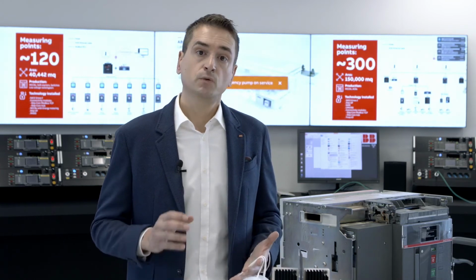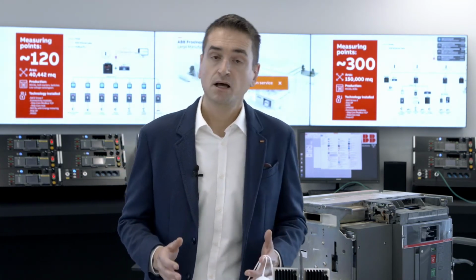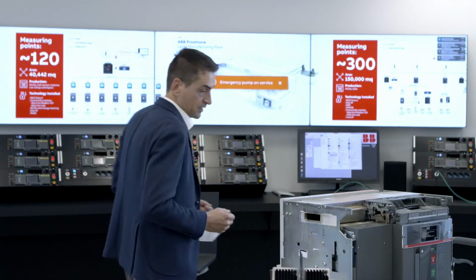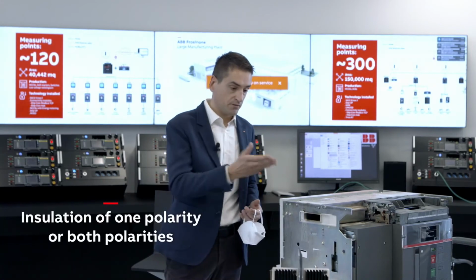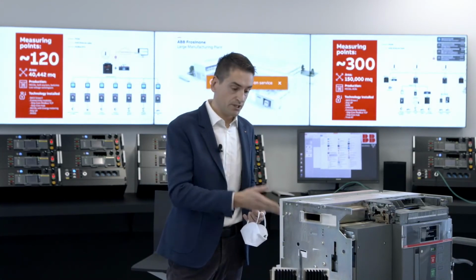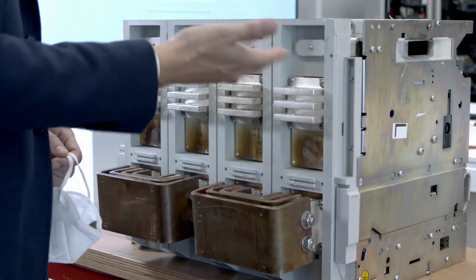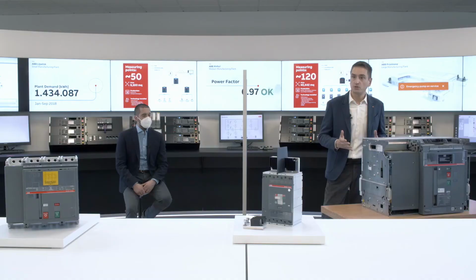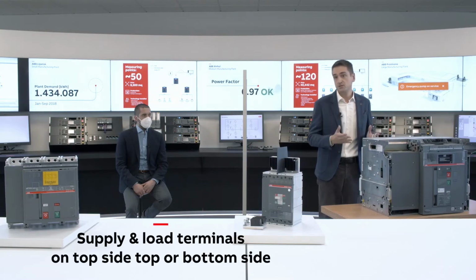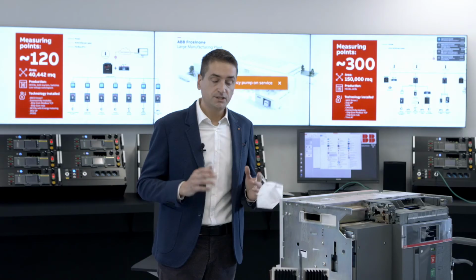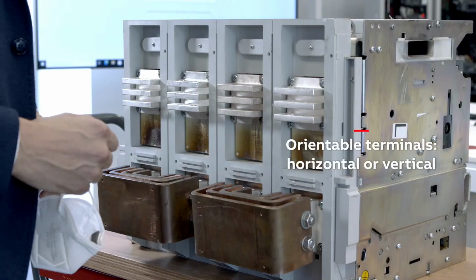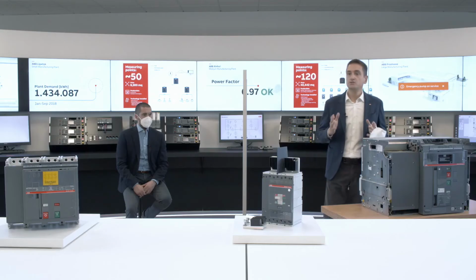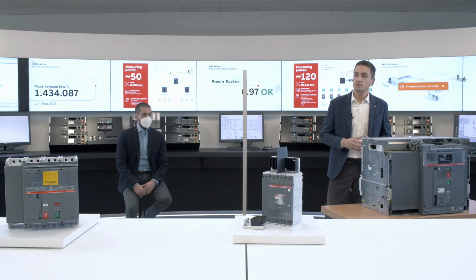One of the main aspects we try to guarantee is the installation flexibility. For instance, in this case, we have the connection of supply and loads from the upper side, and jumpers are provided on the lower side. In this configuration, we are interrupting both polarity of the DC network. We also have the possibility to connect and disconnect just one polarity of the connection. Terminals are provided in vertical or horizontal solution, like the one we can see here. We can use accessory taken from the standard Emax2 offer. So we can use widely known and already available devices on the same platform we can get from Emax2.